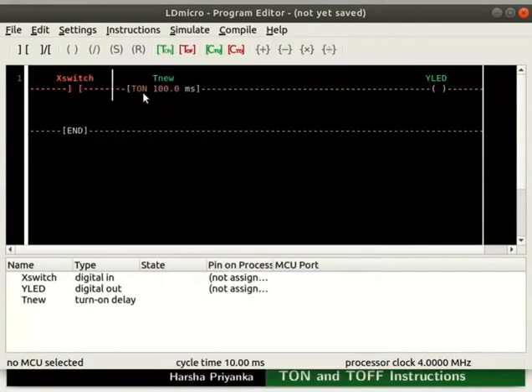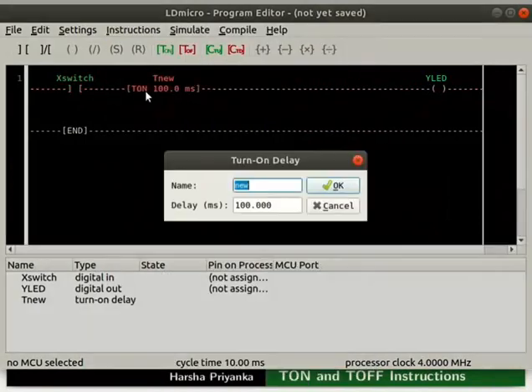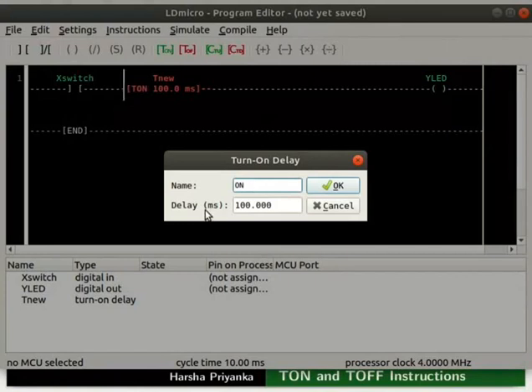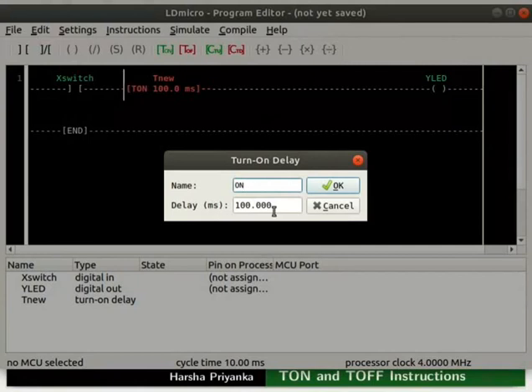Double click on the timer. In the name column, type on. Note that the name will be prefixed by T by default. In the delay column, we can enter the desired delay. Note that the delay is in milliseconds. We will have a delay of 5 seconds, so type 5000. Click the OK button.